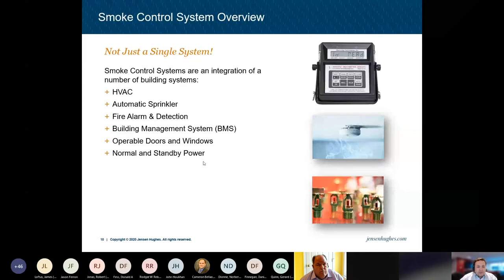So diving into smoke control systems, they're not just a single system. It's not just the fans and the dampers and the ductwork, which is the HVAC portion, but it's an integration of a number of building systems. So you have obviously the HVAC component, but then there's the automatic sprinkler portion, which is used to activate a system. You have the fire alarm and detection, which is either at minimum initiating it, but most of the time, and we'll get into it, is controlling the system.